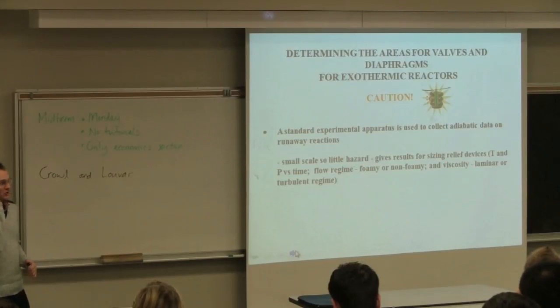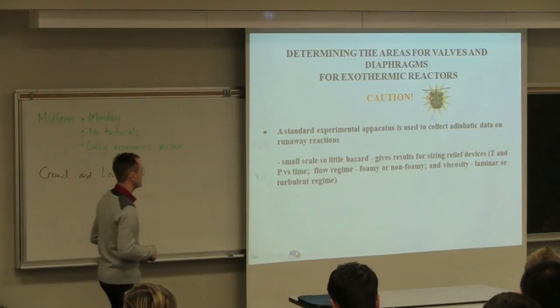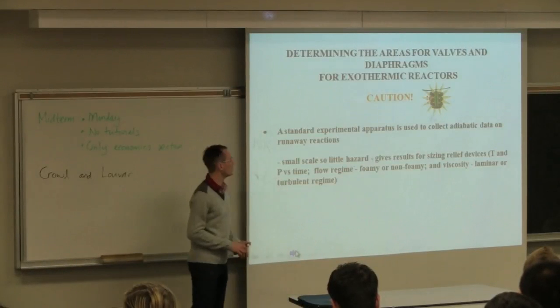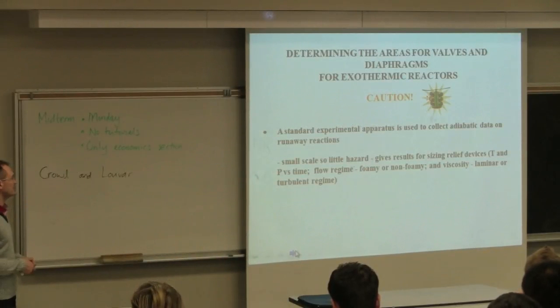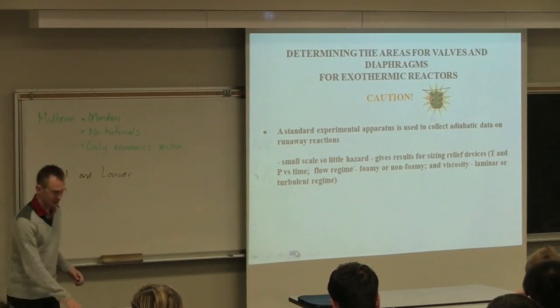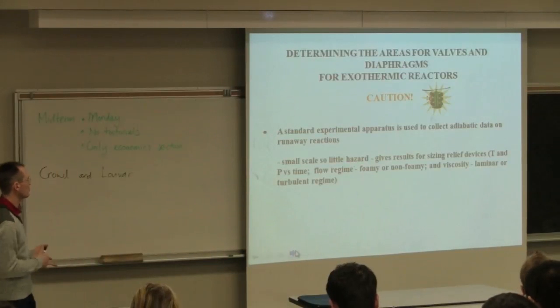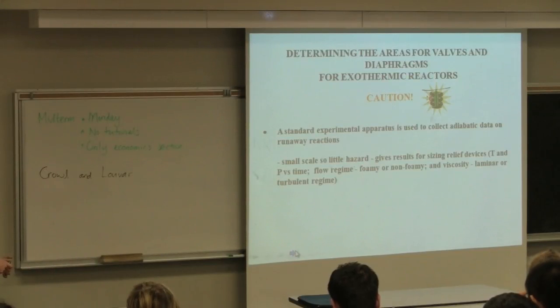In many cases we've seen that when you may have a liquid, that when you relieve it, you actually get liquid and gas coming out of that relief valve. And then your area required for relief is much greater than you incorrectly calculated assuming only a single phase. There are methods to handle calculations for two-phase flow, and should always be considered as a standard that could exist.